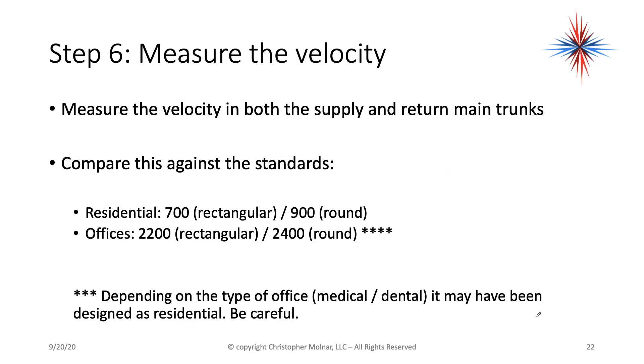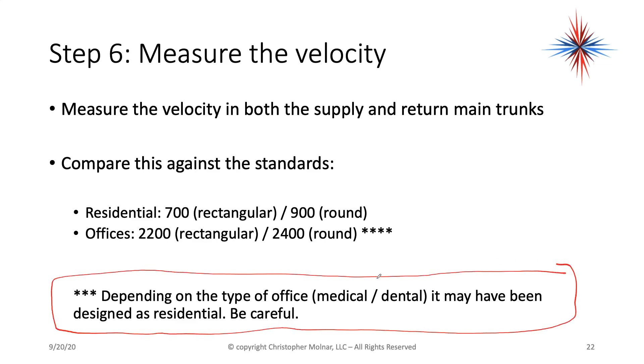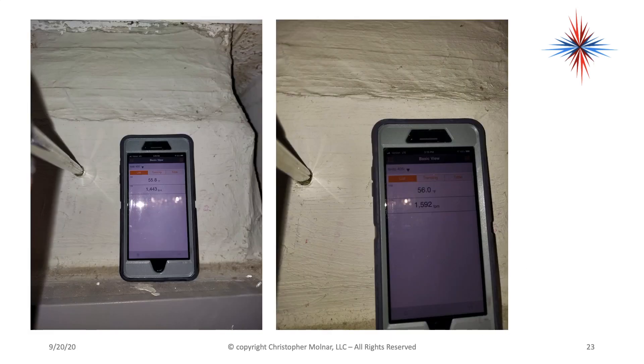There's a note here — be very careful. Depending on the type of office, for example medical or dental, it may have been designed as residential, because the higher the velocity, the higher the drafts and the higher the noise. With the same system we've been talking about, readings came in anywhere between 1,400 and 1,500 feet per minute. That's a problem — it's too fast for residential. Too high of a velocity.